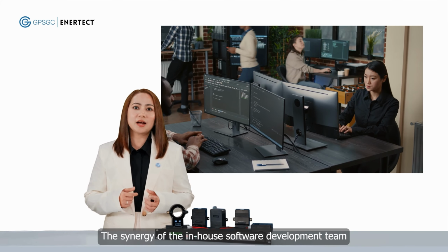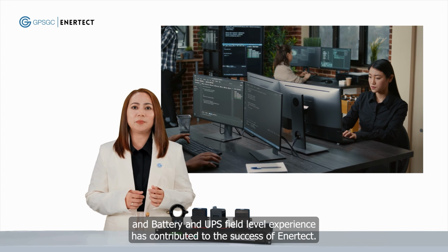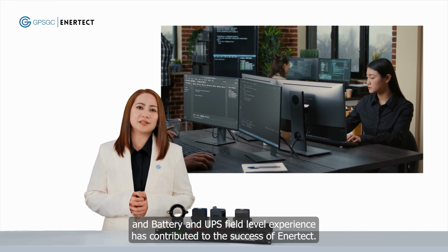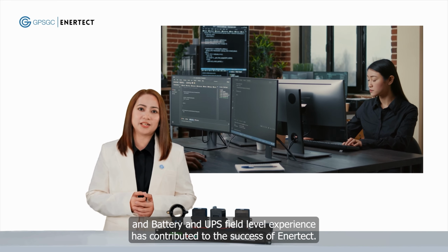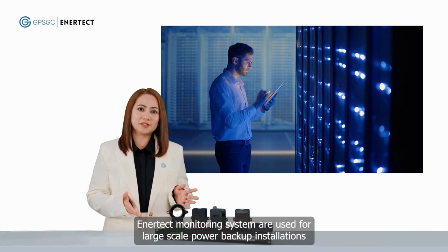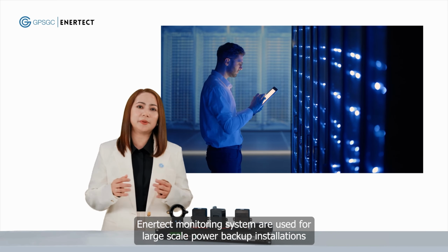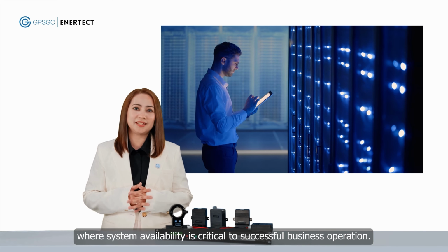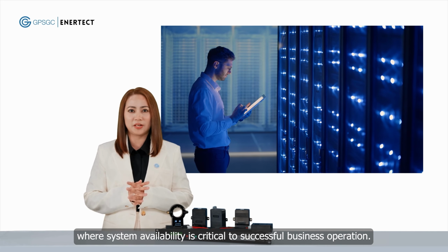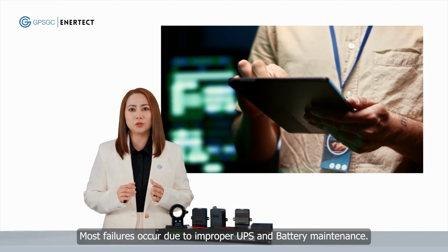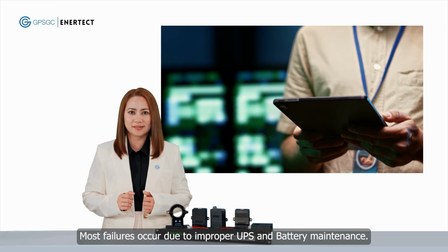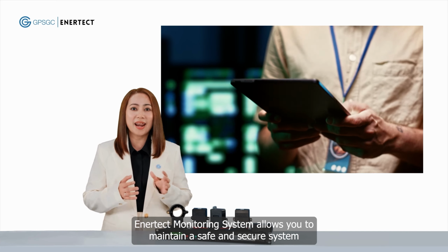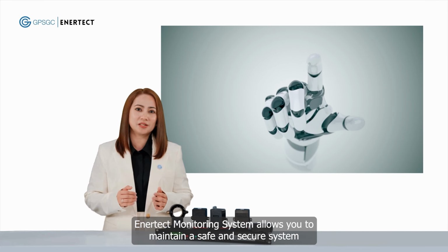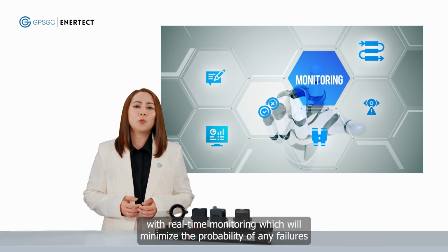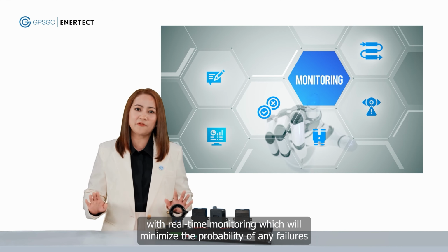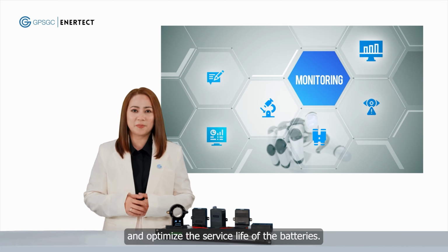The synergy of the in-house software development team combined with battery and UPS field level experience has contributed to the success of ENERTECT. ENERTECT monitoring system is used for large-scale power backup installations where system availability is critical to successful business operation. Most failures occur due to improper UPS and battery maintenance. ENERTECT monitoring system allows you to maintain a safe and secure system with real-time monitoring, which will minimize the probability of any failures and optimize the life of the batteries.